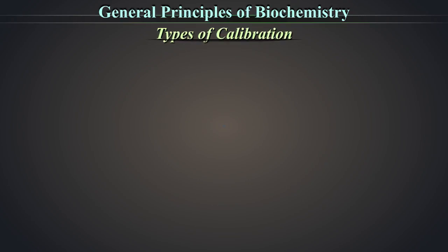Types of calibrations. Single point calibration: A single calibrator of a known concentration is used. This is commonly used for semi-quantitative assays, the single point being the threshold concentration for determining whether it is positive or negative.